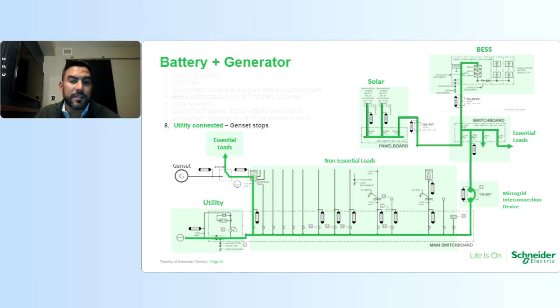And what's unique about this design is it keeps the equipment standardized. So this is still a traditional main switchboard. The microgrid interconnection device comes with the controller. It signals your microgrid system to come online in island mode, really keeps everything standardized. And again, this was a K through 12 application. So, bid spec jobs, we want to keep the pricing competitive and keep it really standardized. So we're really not providing an over premium, over specified product for the application.